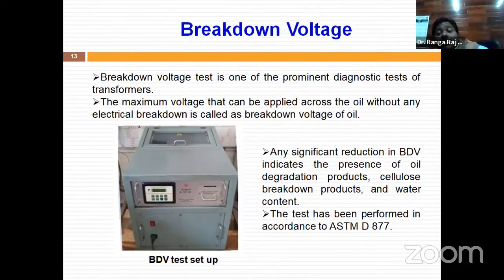So, breakdown voltage test is one of the prominent diagnostic tests of a transformer. We all know this, it's a basic test - in every substation we find this equipment for the breakdown voltage test. The maximum voltage that can be applied across the oil without any electrical breakdown is called the breakdown voltage. If the oil is weak, then with small electrical stresses we find so many arcs. If there is water content in the oil, there is formation of arcing, which is very, very dangerous.